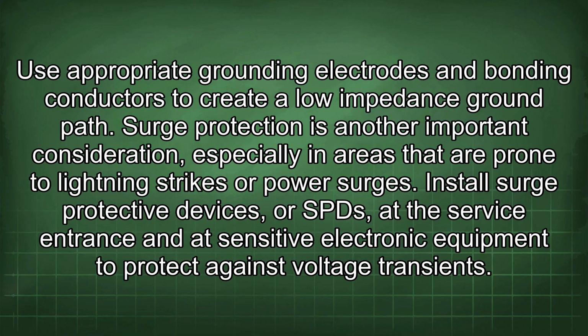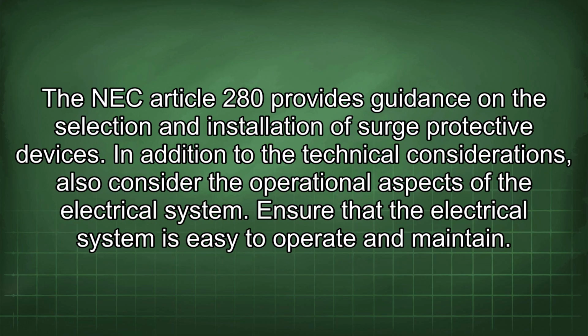Surge protection is another important consideration, especially in areas that are prone to lightning strikes or power surges. Install surge protective devices, or SPDs, at the service entrance and at sensitive electronic equipment to protect against voltage transients. The NEC Article 280 provides guidance on the selection and installation of surge protective devices.